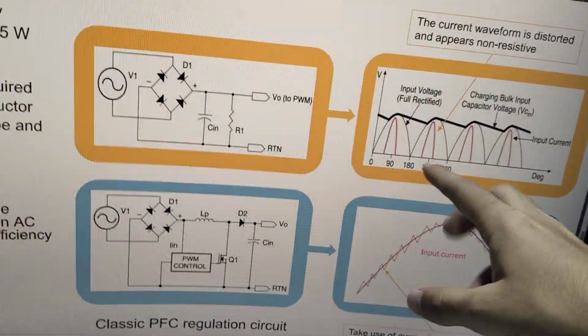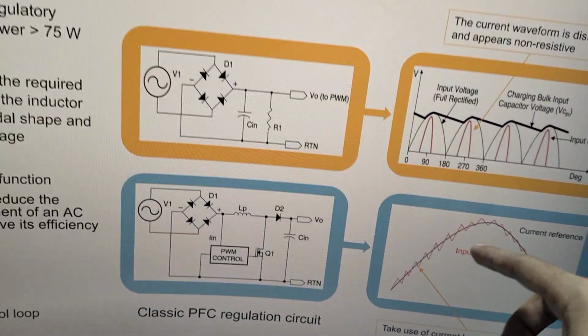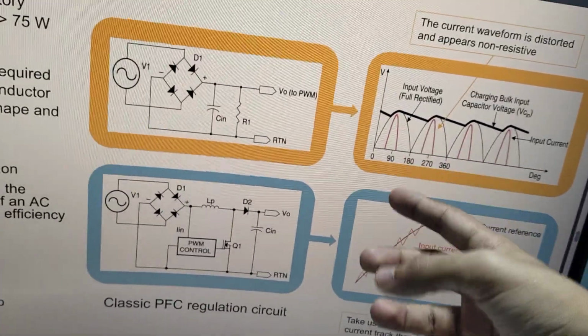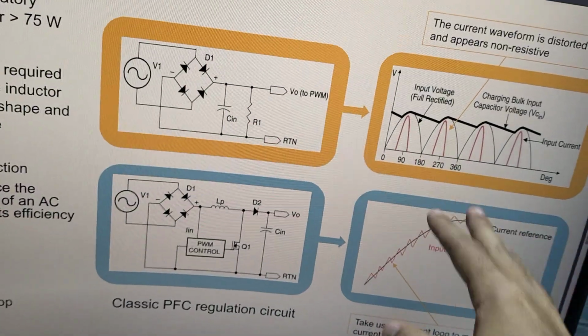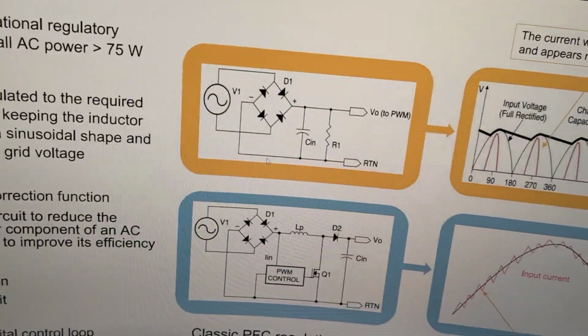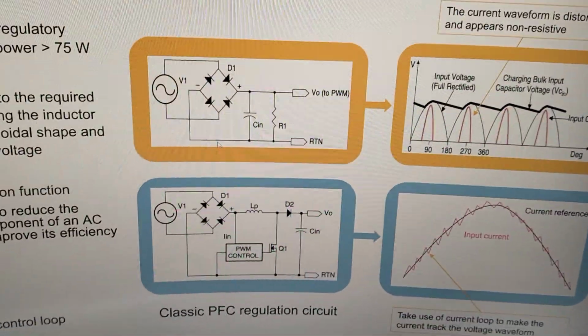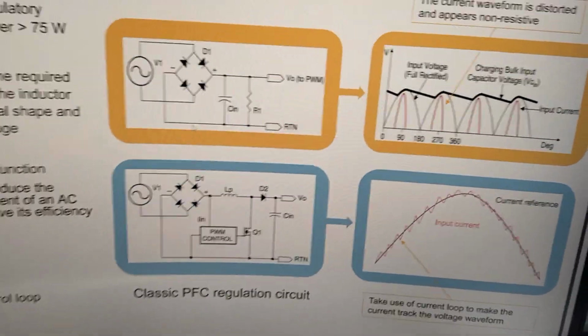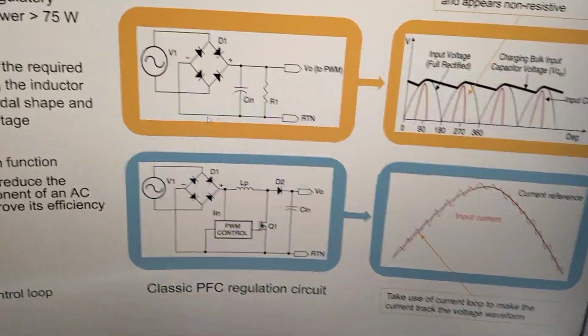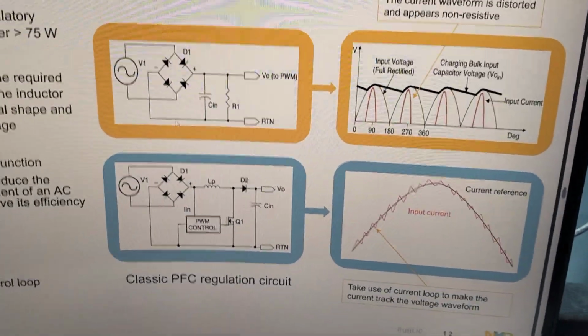If you try to find the power factor, which depends on both voltage and current, it's generally really bad - almost 0.6, 0.7. So you draw more current and it's not useful current, so you need thicker wires, and overall efficiency reduces.